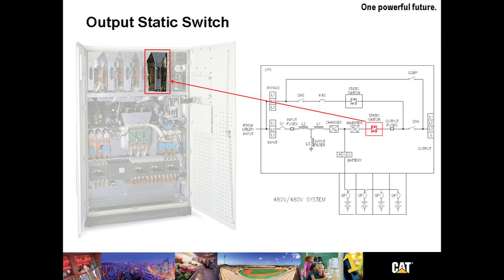One over from the inverter is the output static switch. The output static switch and the bypass static switch work together to assure the load is always powered. If there is ever a failure on the input, the static switch would provide a no-break transfer to the bypass, assuming of course the bypass is still within tolerance.